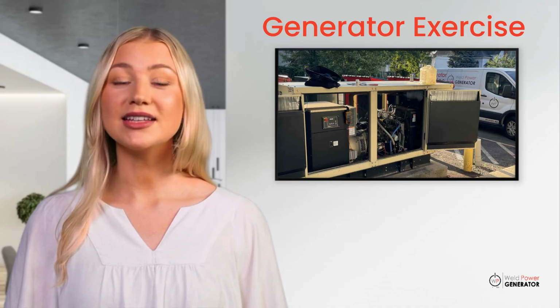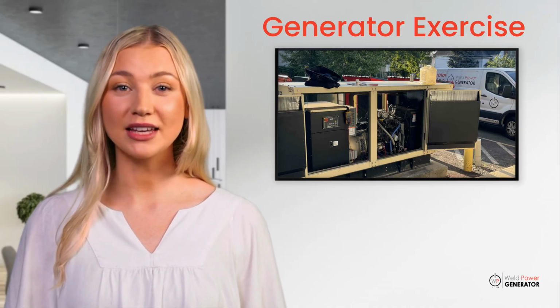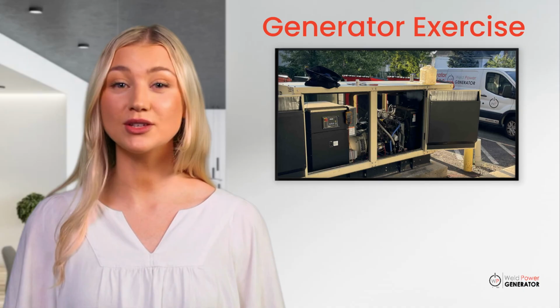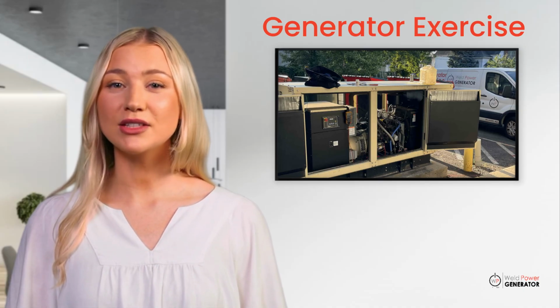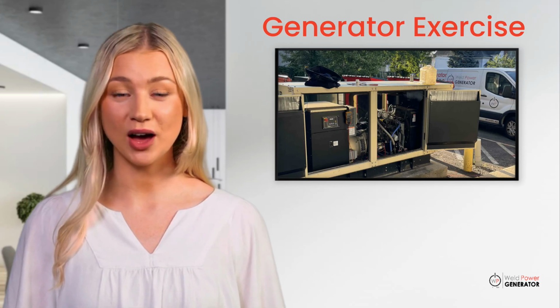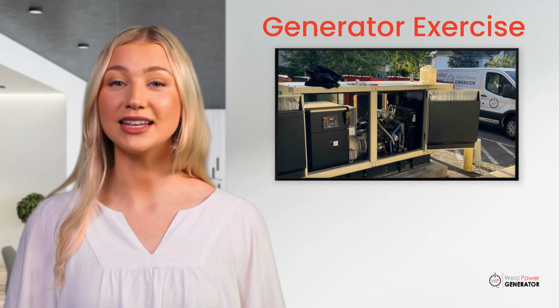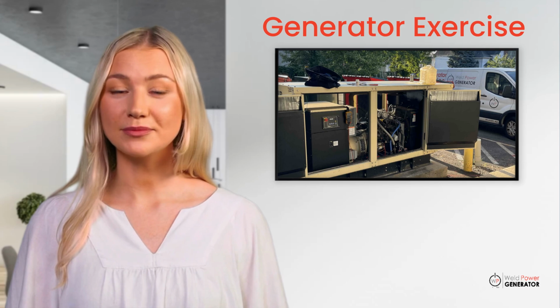The best practice is to schedule annual building load testing or load bank testing to ensure your generator exercises at 25 to 30% of its rated capacity or higher. This will improve reliability and extend the generator lifespan.